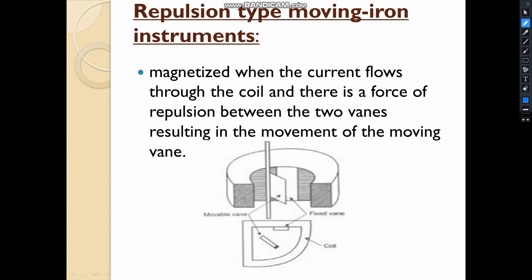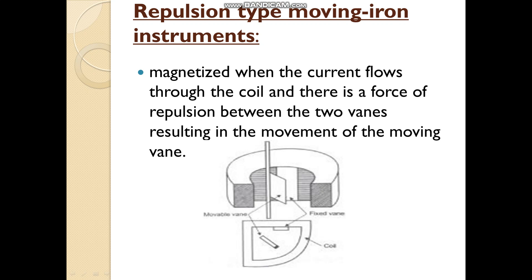In the repulsion type, the main difference is that there are two vanes — one fixed vane and one moving vane. The moving vane tries to move to the position of minimum reluctance such that inductance will be high. Under the repulsion type, there are two sub-types: radial vane and coaxial. In radial vane type, the vanes are radial strips of iron, whereas in the coaxial type there are sections of coaxial cylinders.